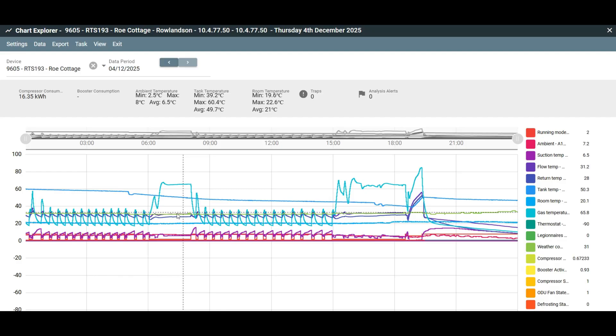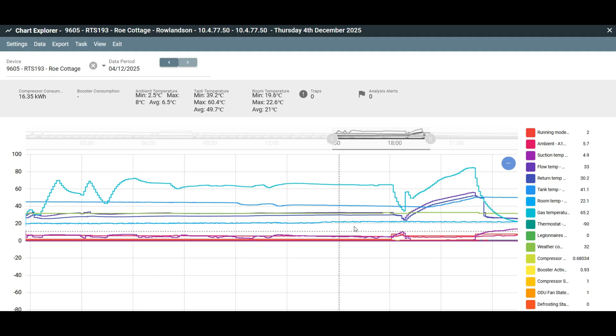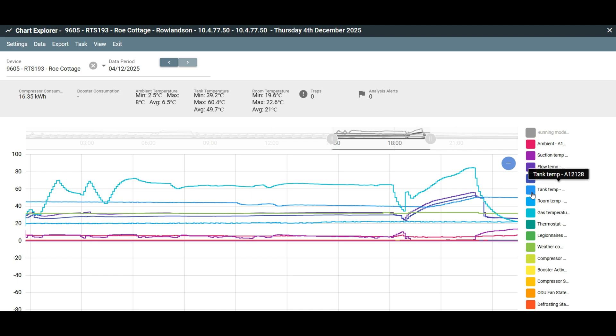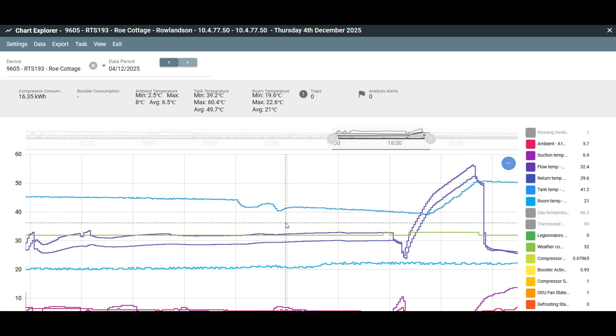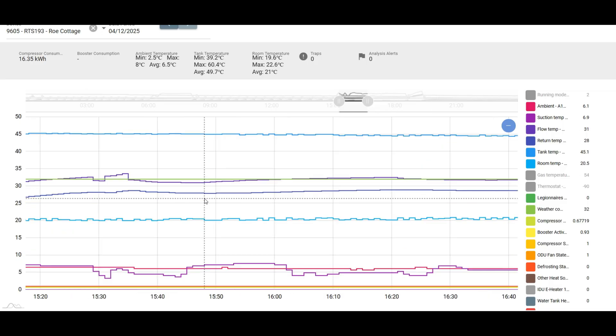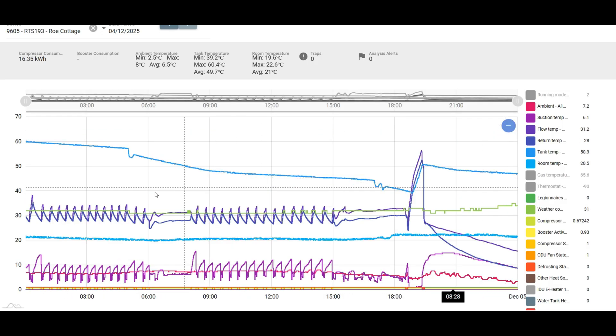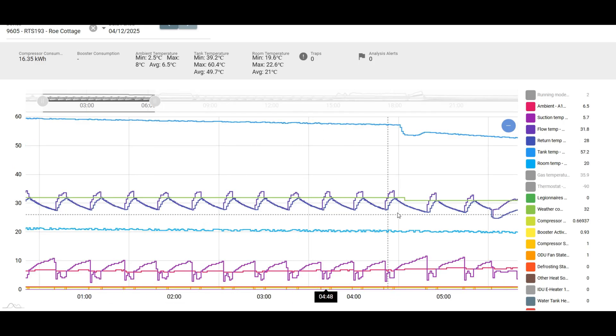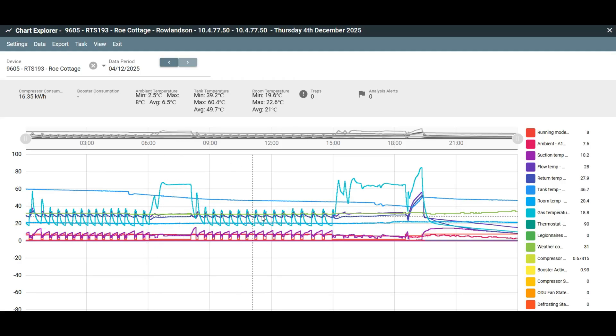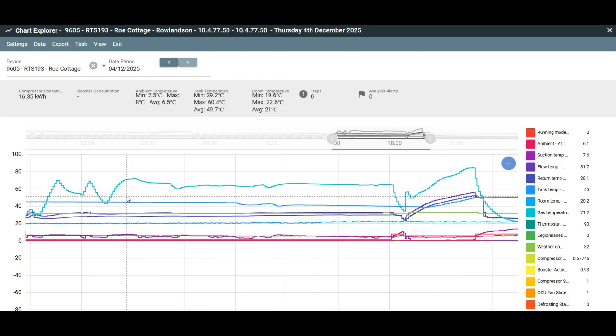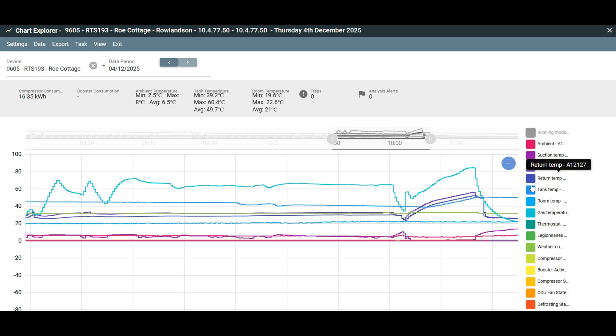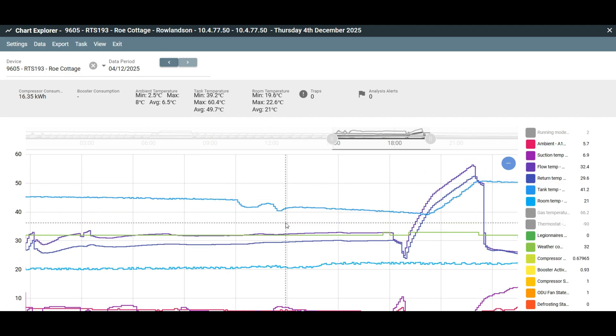I'll quickly show on screen what our data looks like when we receive it and what the graphs look like. We can populate any of the inputs or outputs that the heat pump has. Inputs are the sensors — flow sensor, return sensor, tank sensor, room temperature, outdoor temperature, refrigerant pressures — and outputs are what the heat pump is commanding: its heat exchanger pump, three-port valve, booster heater, compressor speed, hertz it's running at, flow rates, and the modulation demand on the pump. We can monitor any one of them.